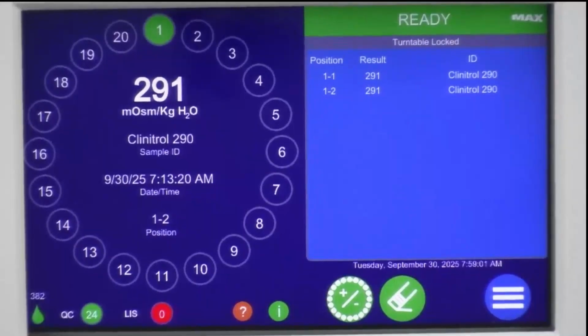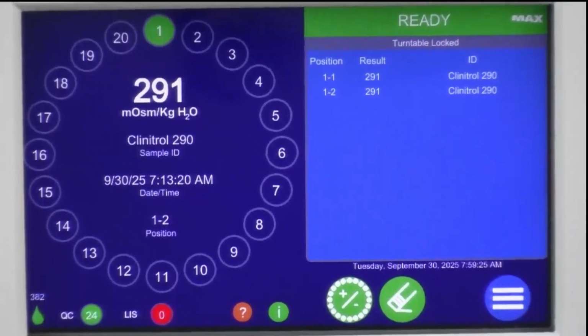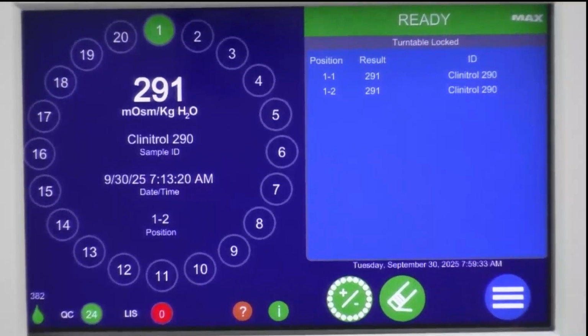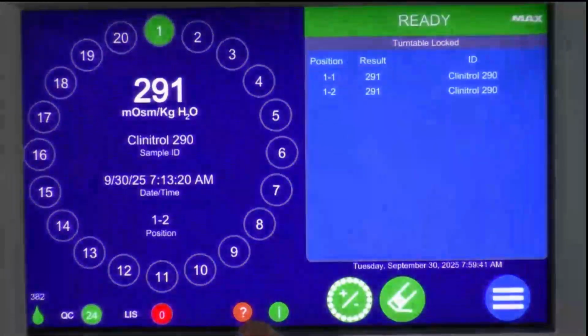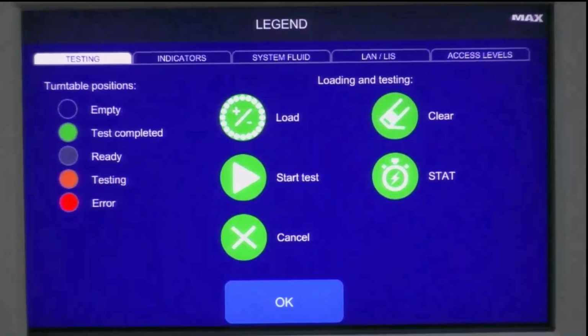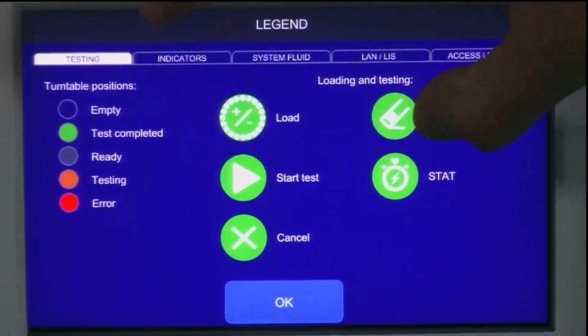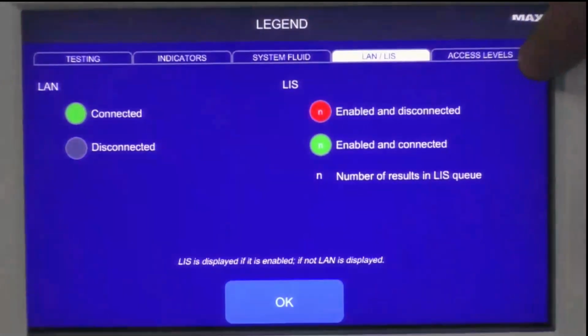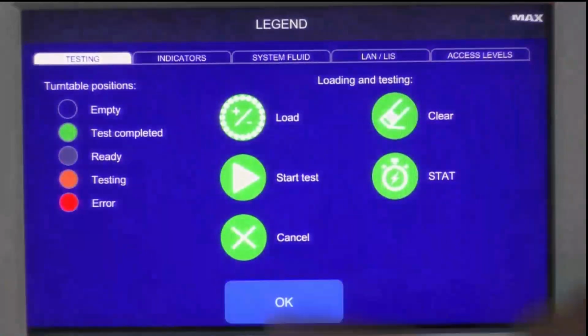LIS, where it says 0 there, and it's red, if that were green, we know that the LIS is connected. Because I don't have it connected to LIS here in our demo room, it's red. If I were to send patient results through to the LIS right now, or attempt to send patient results through to the LIS right now when it's disconnected, that number would go from 0 to however many results I'm trying to send through. And when I show you the result menu, I'll also show you the ability you have to manually push those results to the LIS. For example, if I were to regain connectivity, I had some LIS downtime, which unfortunately and frustratingly so happens from time to time. Here where this little question mark is in the middle, that's going to open up a handy dandy legend, which is going to basically highlight and outline all of the different indicators that you might see in the user interface. So if you're ever confused about what something might mean, then you can go here and find that out.